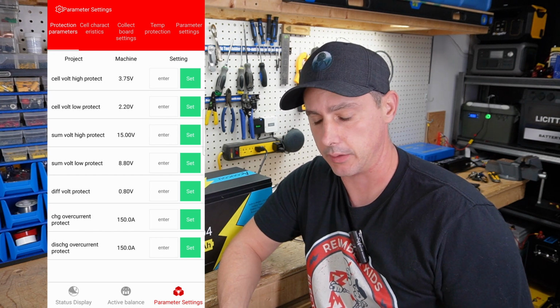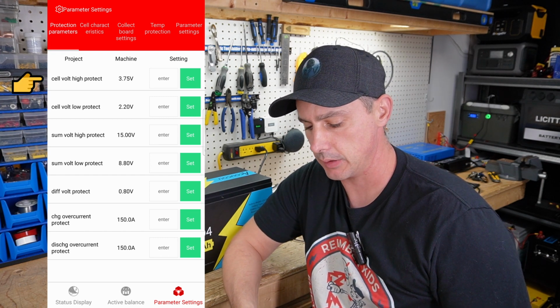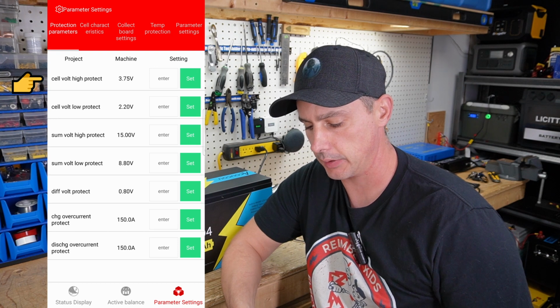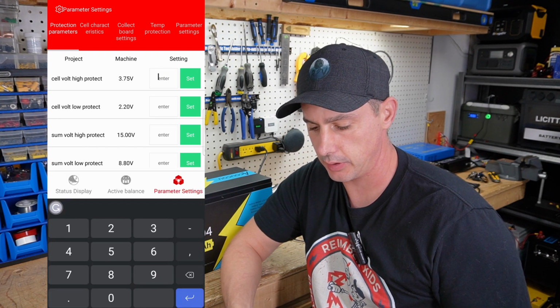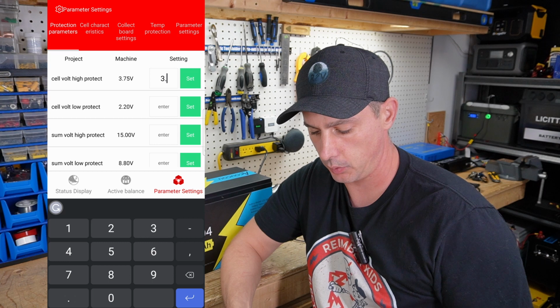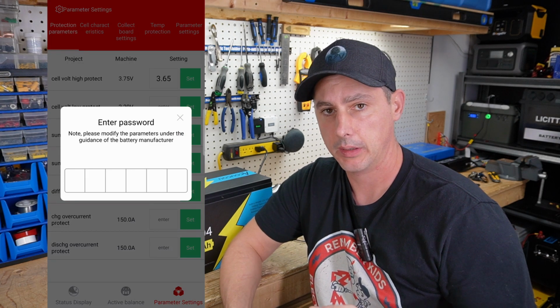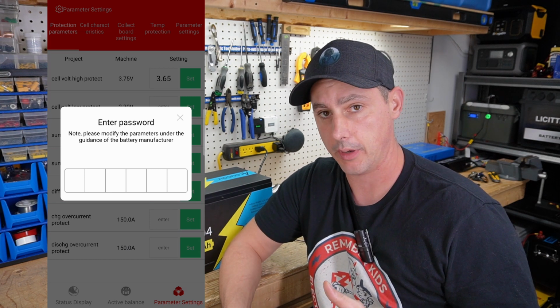Now here's some of the settings we need to change. You can see cell voltage high protection - we actually need to change that to 3.65. What that's going to do is, if one cell goes above 3.65, it's going to cut the whole pack. It should never happen, but this is why we have protections.